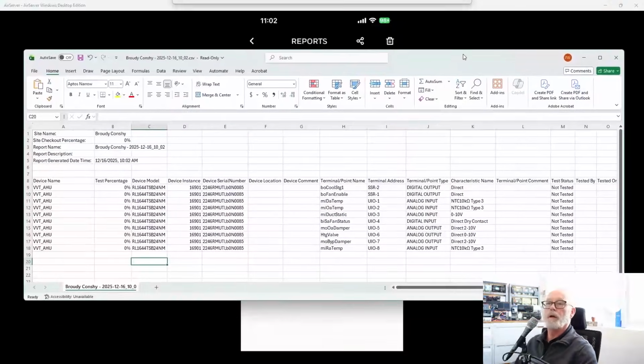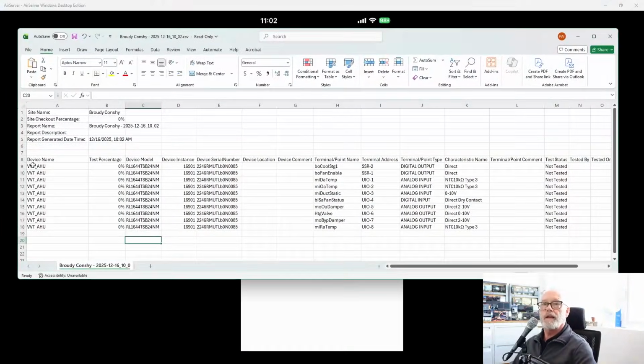So what we'll do is I have one here of what one would look like, and basically it gives you a list of all the I/O, their terminal assignments, and then the point type as well as the characteristics of a point. So it's a good report to have just for checking to make sure your configuration is correct in your programming. Make sure you have the right I/O on the right terminals, and then also the right characteristics for your points.